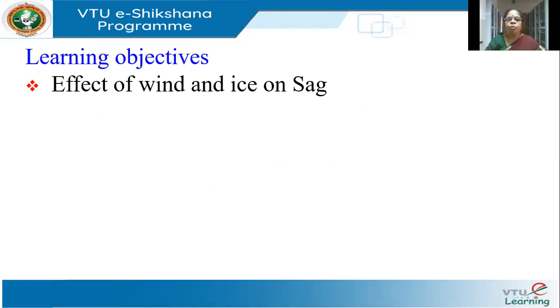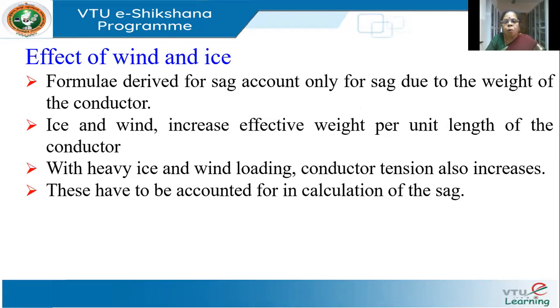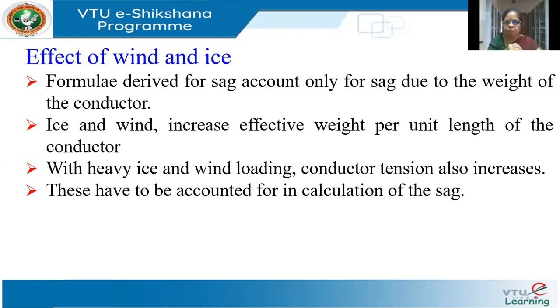In this class we will see the effect of wind and ice on SAG. Wind and ice are very common — ice may not be present everywhere, but wind exists to varying degrees depending on the geographical location. We will derive the formula for how to account for wind and ice when we determine the SAG. If there is a deposition of ice on the conductor, the weight of the conductor will increase. Wind will try to give a lateral force to the conductor, and we have to account for these when calculating SAG.